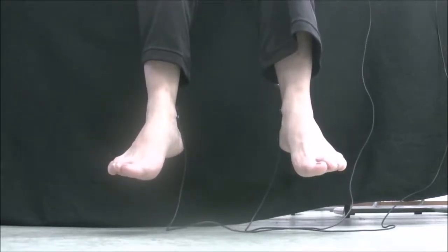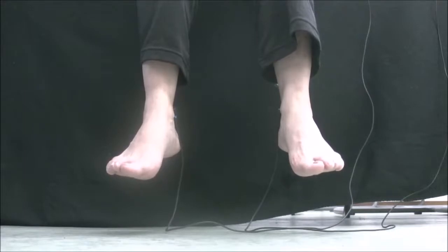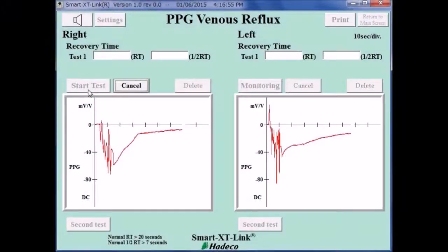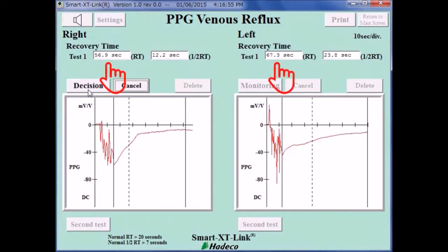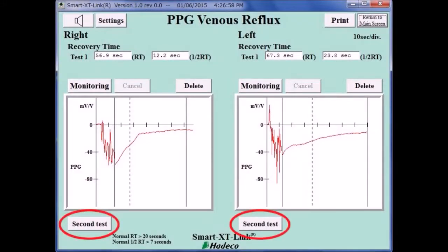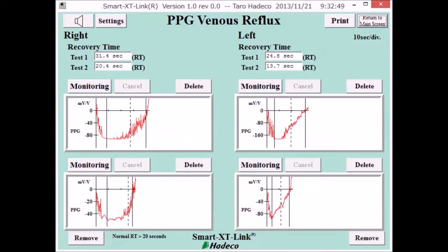Ask the patient to flex his foot normally 5 times, synchronizing with the beep sounds. Adjust the sound volume on your computer for the beep sounds. After the exercise, ask the patient to relax his foot and remain still. After the waveform returns to the baseline, the XT will automatically freeze and save the waveform and show the recovery time. Click Second Test to add the second test window on the screen if necessary.